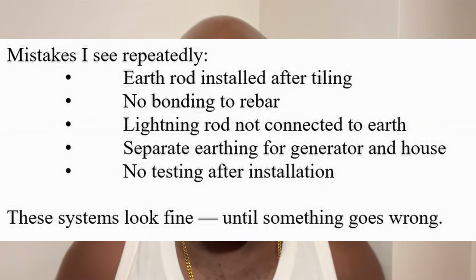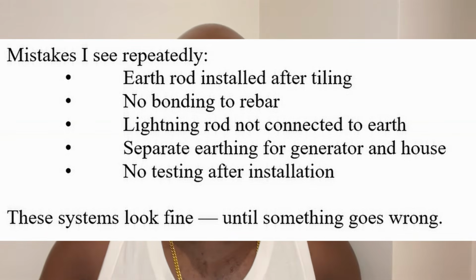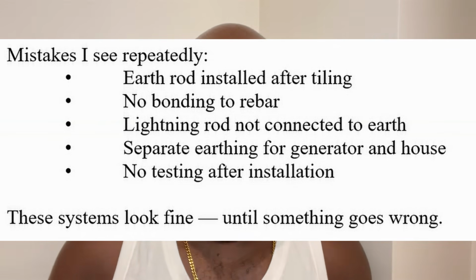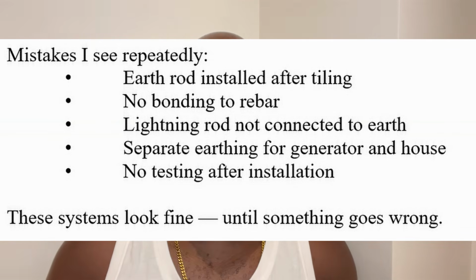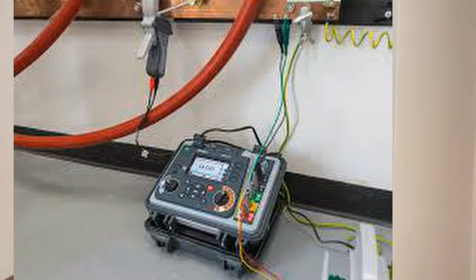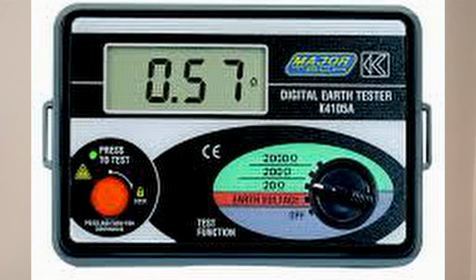Testing and verification. A proper system must be tested using an earth resistance tester. Picture on your screen. Continuity testing. Bond verification. If the resistance is too high, let's say above 10 ohms, then you need to add, if you haven't done the foundational earth system, then you will need to add supplementary earth rods in the ground, improve soil contact, increase the earth conductor length, and interconnect the rods together, provided they are spaced apart sufficiently. It's never guesswork. It's always a test.